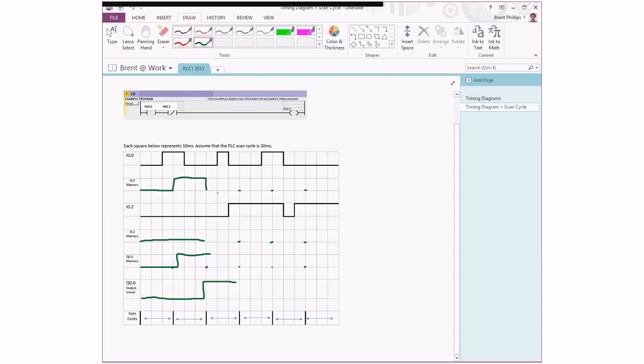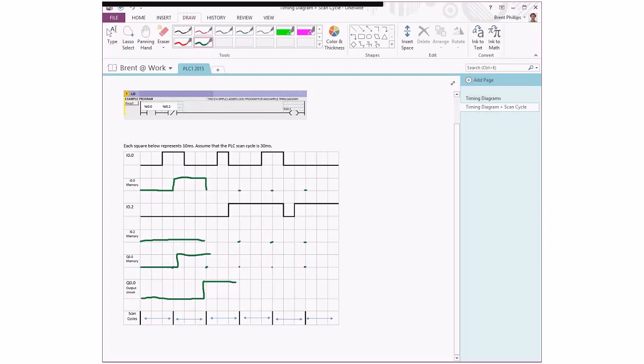So just to recap, at the start of our scan cycle we have the state of our physical input being copied into the memory of the PLC, and then in the middle of the scan cycle we have the ladder logic being executed. So the ladder logic up here uses combinations of inputs controlling the output, controlling the memory part of the output. And then at the end of the scan cycle, that memory value gets transferred to become a true state in the output circuit.